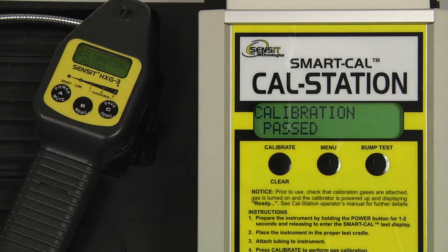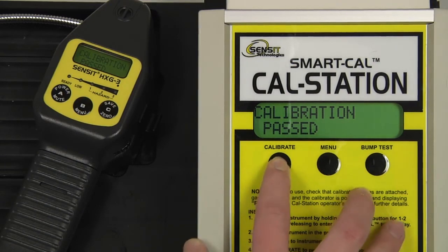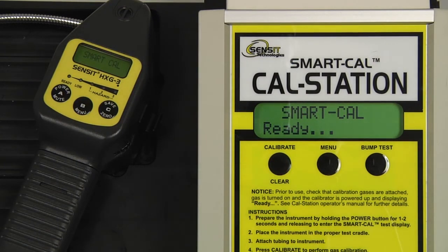Calibration has passed. We can remove the instrument hose from the end of the gooseneck, exit out of the calibration mode on the cal station by pressing and releasing the calibrate or clear button, and exit out of the Smart Cal mode on the instrument by pressing and releasing the A button. Allow the instrument to clear for 60 seconds or until the display reads 0 before powering the instrument off.